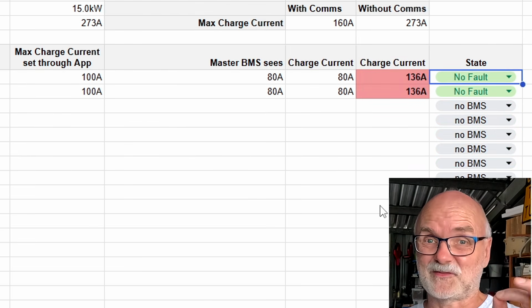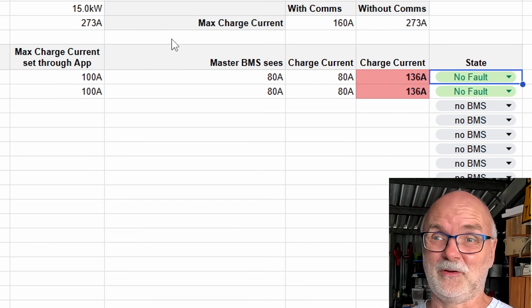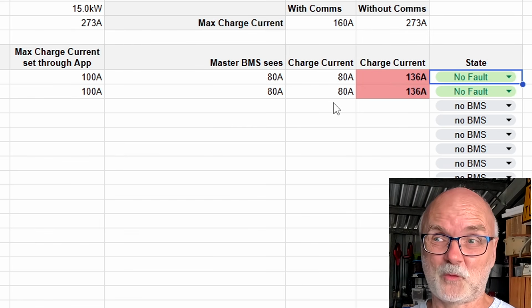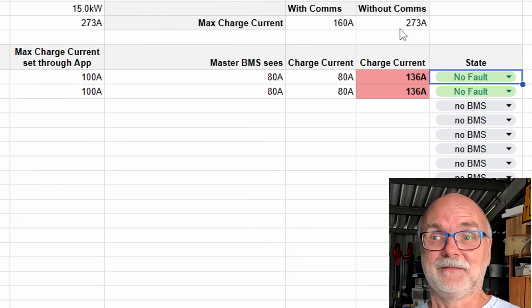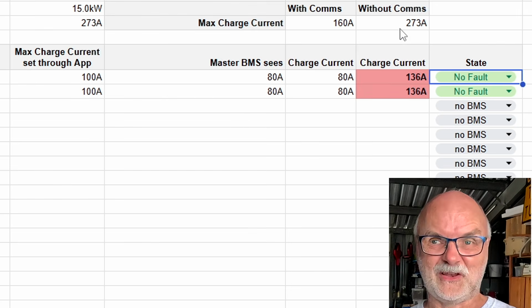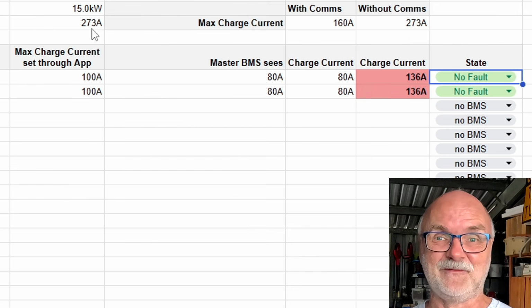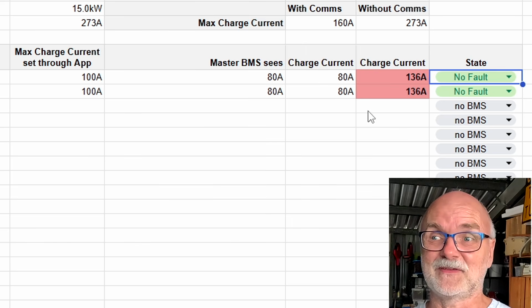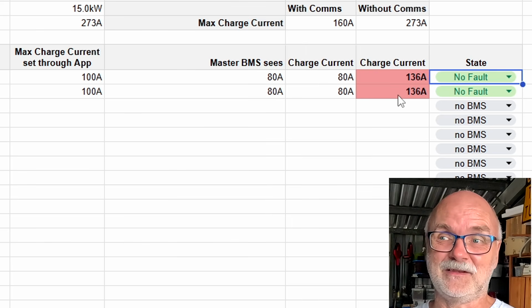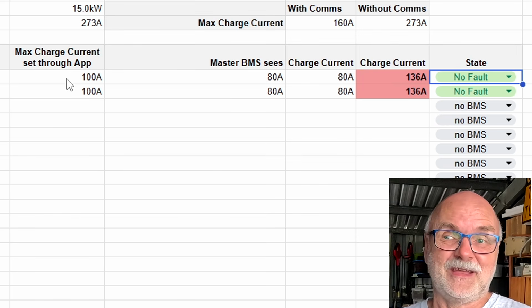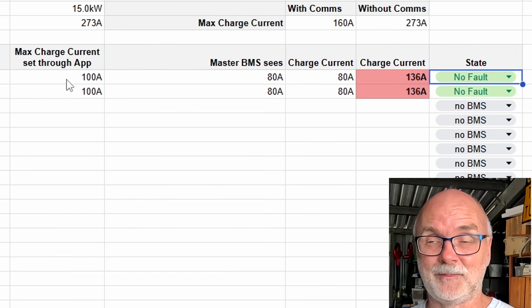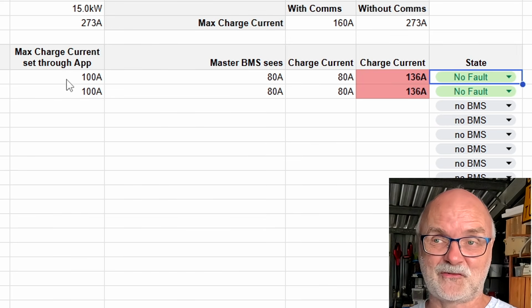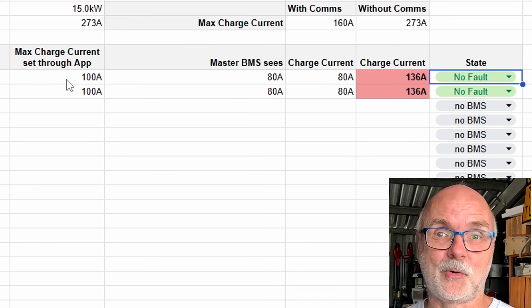And only if you have a smaller system like this with 2 batteries only and have a 15 kilowatt solar system, this would not even work without communication, because now the charger does not know about your batteries and charges full power with 270 amps into your 2 batteries, and you're already over these 136 amps. Of course, you can increase the maximum charge current per BMS, but your cables and your circuit breaker, your fuse, needs to support this as well.